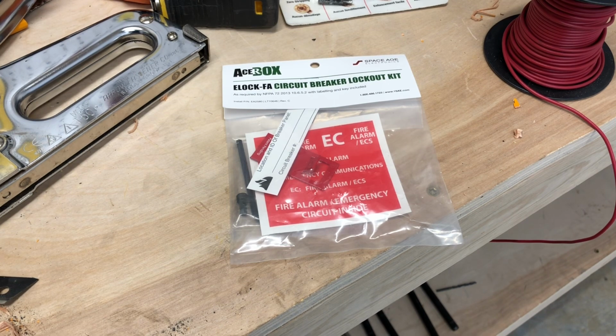Now this is not a lock-off for safety reasons. This is a lock-on specifically made for breakers that are supplying power to a fire alarm panel or some sort of fire life safety equipment.